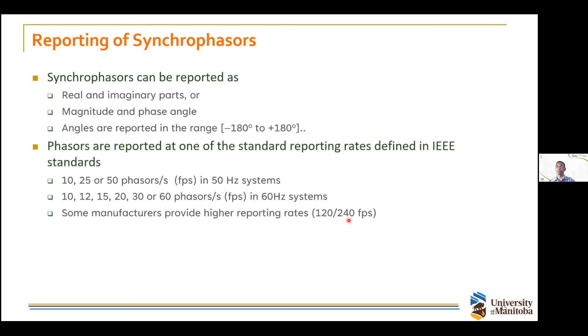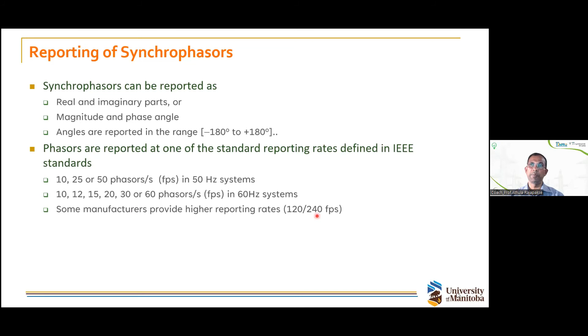And of course, there are devices which can report higher rates. For example, in a 60 Hertz system, you can report 120 or 240 FPS. PMUs are available with this capability, but the standard only specifies up to a certain rate. Now, look at what happens. Our measured signal is not exactly 50 Hertz or 60 Hertz, right? Our reference cosine function is defined assuming it is 50 Hertz or 60 Hertz, depending on the system. And so its frequency is different from the signal's.